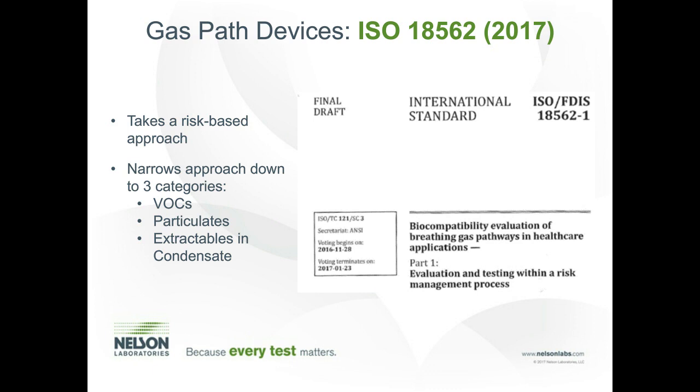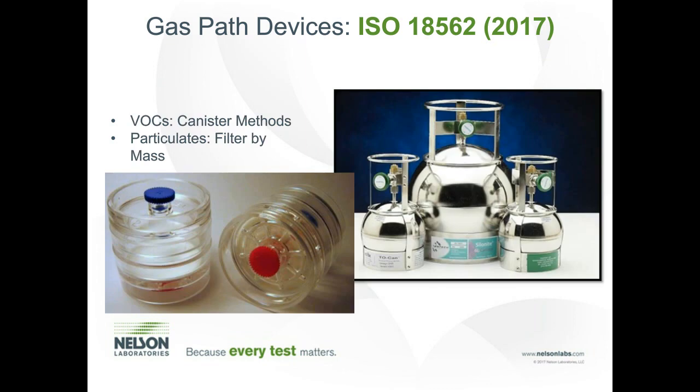risk-based approach. The way this is done, to do the volatiles and the particulates, it's basically a common sense approach. You think about how the device is used clinically. You take a worst-case approach where you say, okay, this is the hottest temperature the device could run at, and this is the longest time, and you try to sample the gas that passes through the device into a canister, and then you analyze any compounds that were inside the canister. So I think it makes a lot of sense. It's a really great approach.